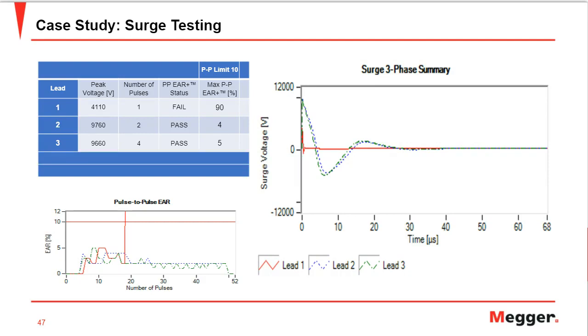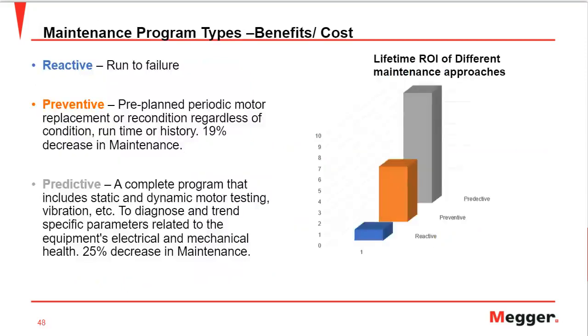So we'll see the maintenance program and what the types and benefits of the maintenance program are. There are three types of maintenance programs. Reactive, which is run to failure: we let the motor run until there's a failure detected on that motor. Preventive maintenance program is conditioning or checking the motor at particular intervals during the year, even if the motor is in good condition or running regular operations.